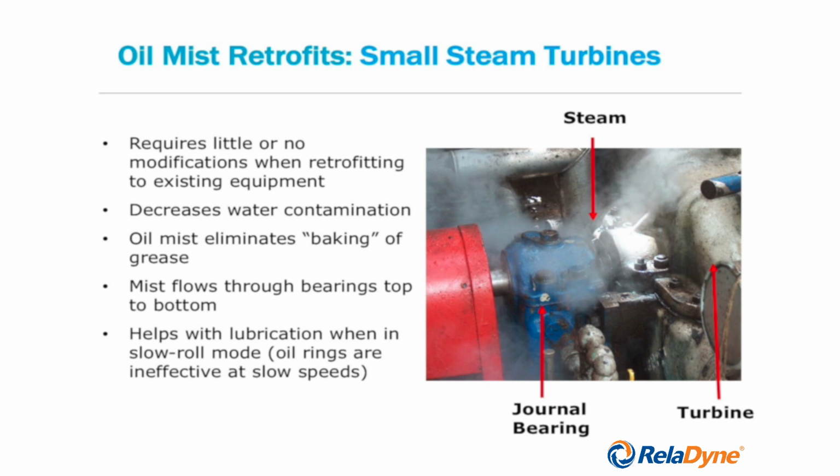The oil mist flows through the bearing top, and it goes perhaps out to the side. Liquid oil or grease is kept in a bearing of this type, and the oil mist routing is described in some of the literature that you can get from Colfax Reliability Services. They have very clear-cut instructions that allow you to follow point by point and to do this kind of work even as the machine is running.